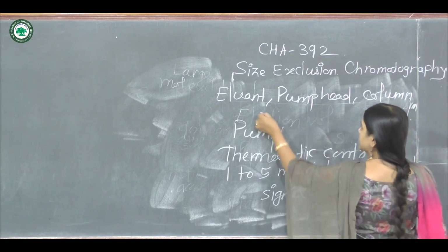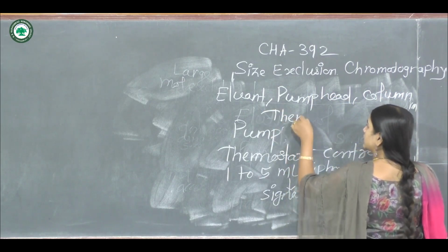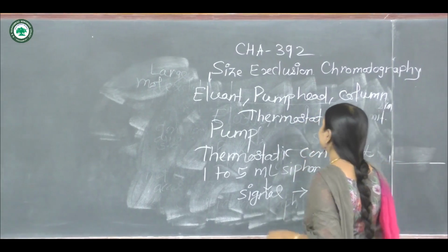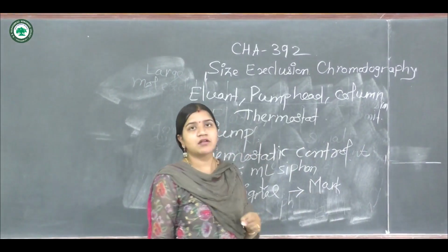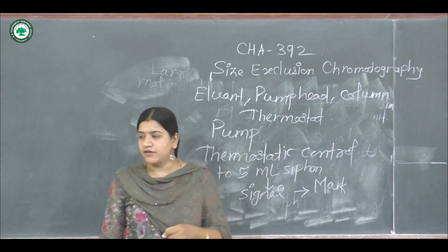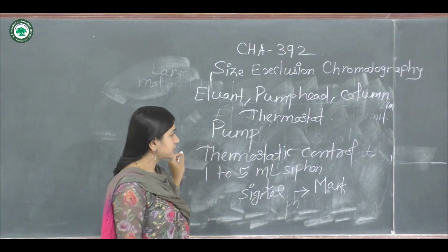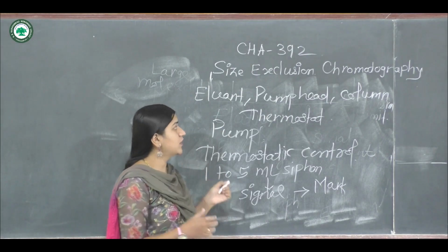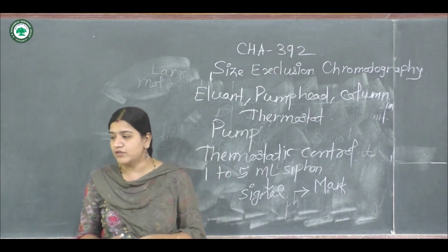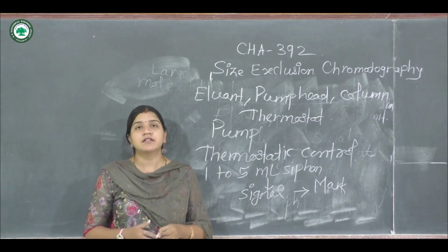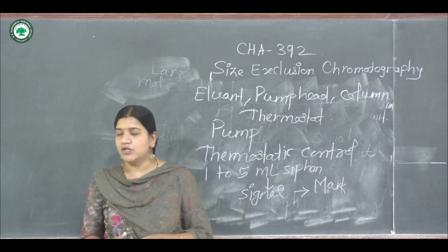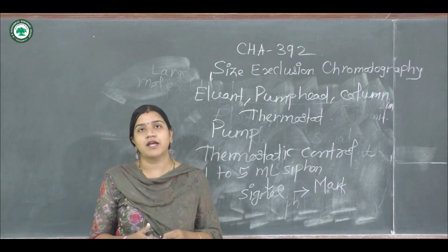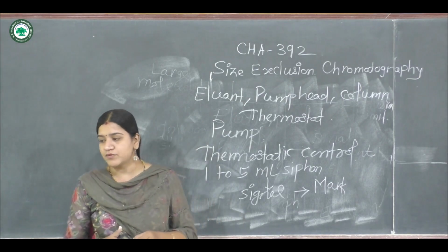All these three aspects should be thermostated. After thermostating the eluent, pump head and column, the retention volume is more accurate and you will obtain a more accurate result.